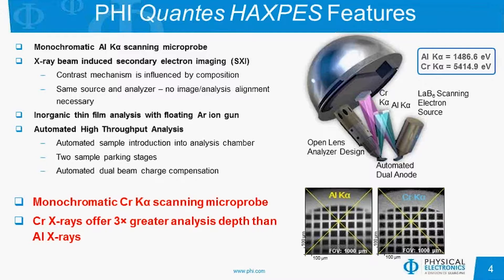The QUANTES has a focused monochromatic chromium K-alpha X-ray source, which offers three times greater analysis depth than conventional XPS. We use the same electron gun to generate the aluminum K-alpha X-rays, but we have two different monochromators. We can take SXIs using either of the X-ray sources to ensure they are aligned, and all switching between the two X-ray sources is automated, taking about one minute to switch between the two.